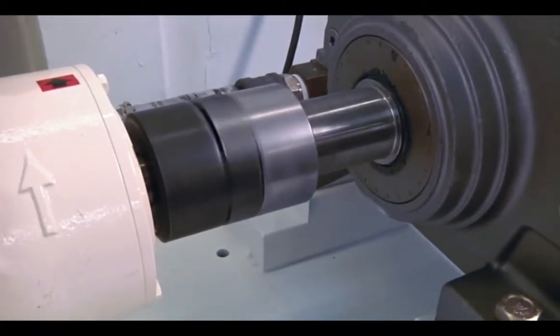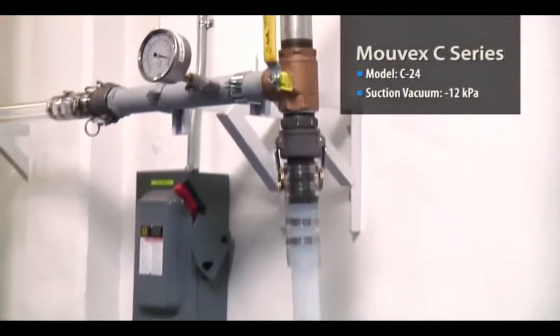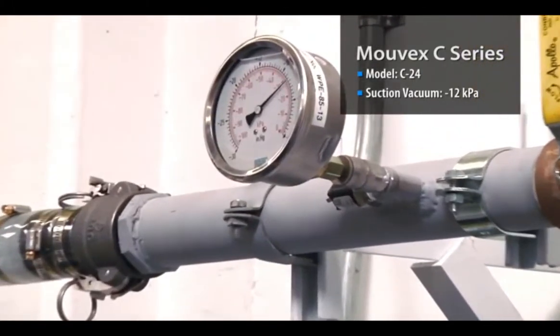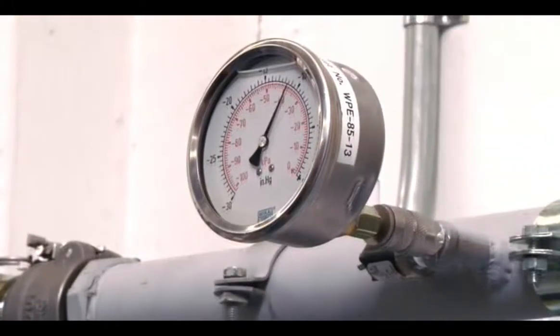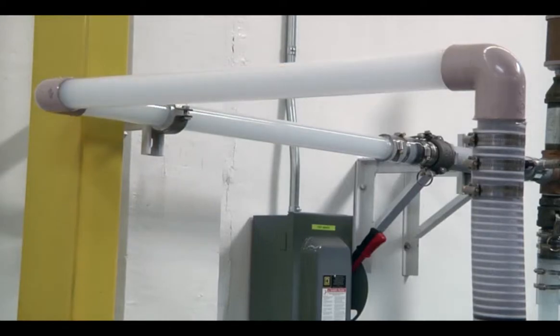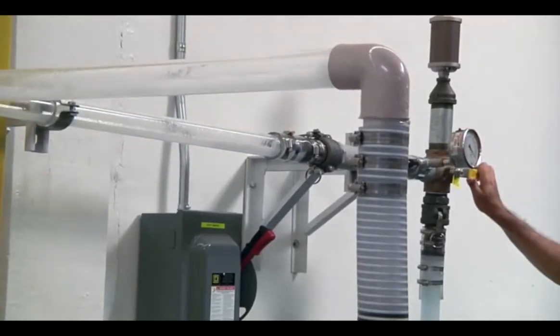On the suction side, this C24 creates a vacuum of minus 12 kPa to dry prime and pull the liquid up the suction column. The Mouvex pump can run dry and creates the suction required to fill and prime the pumping chamber, as well as suck the line dry upon completion.